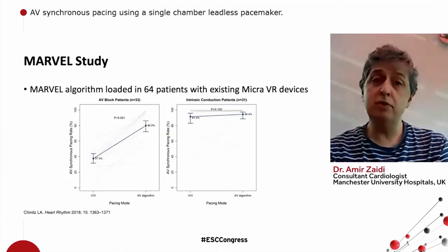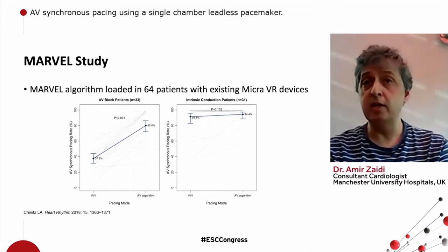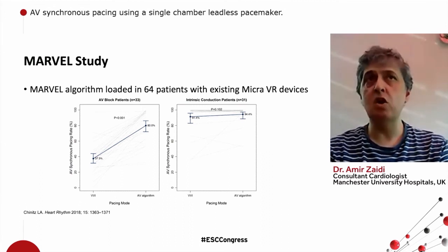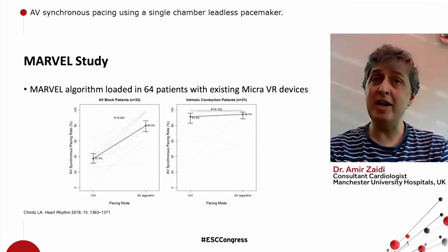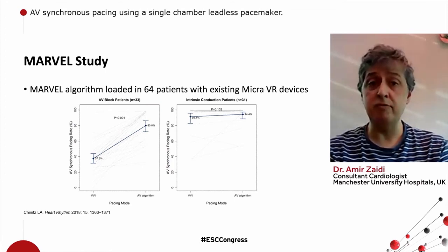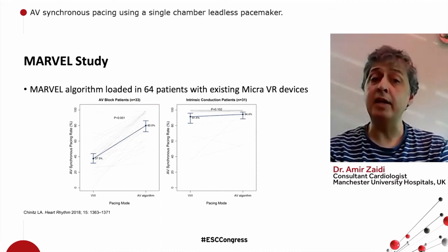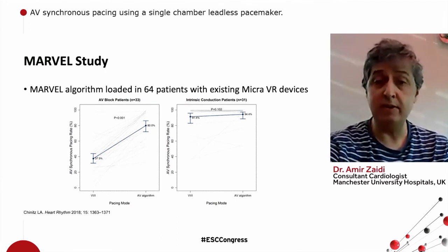And we've looked at the use of the algorithm in patients with existing VR devices. I would stress that this is not something that allows backwards compatibility on existing VR devices, but software can be written onto existing Micra VRs, which allows short periods of the AV synchrony algorithm, the Marvel algorithm, to test the use of AV synchrony.